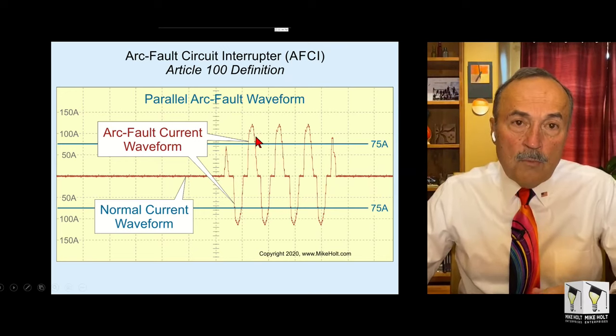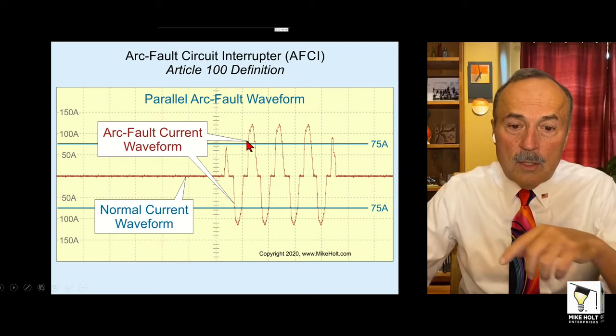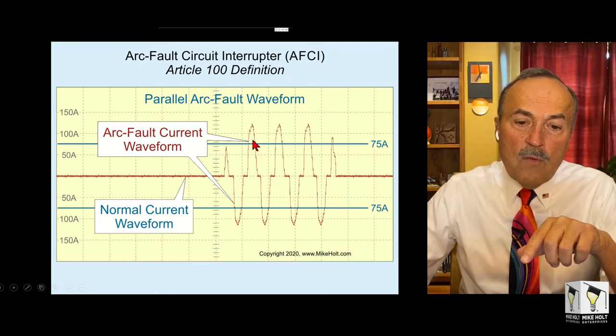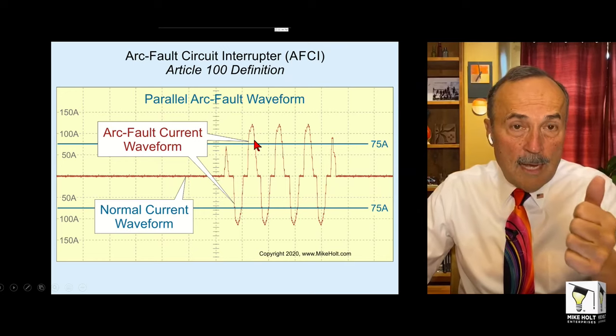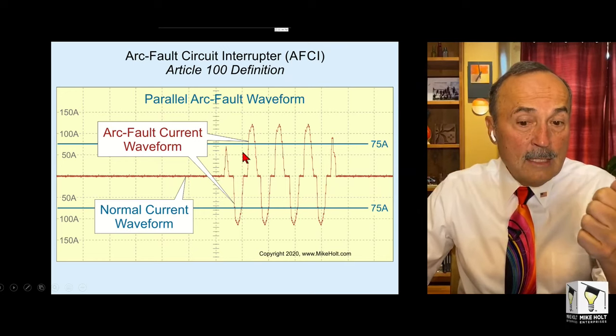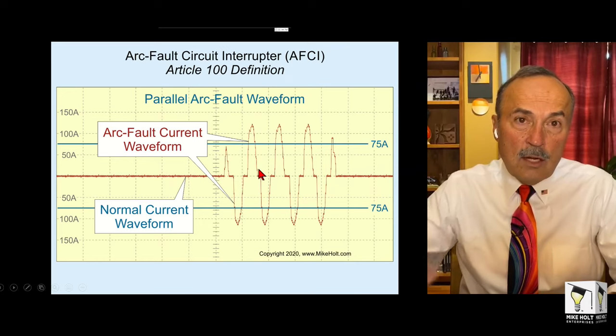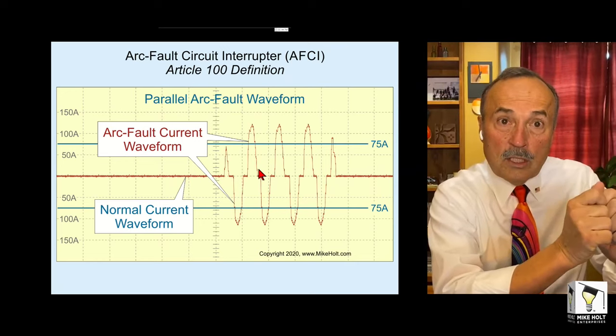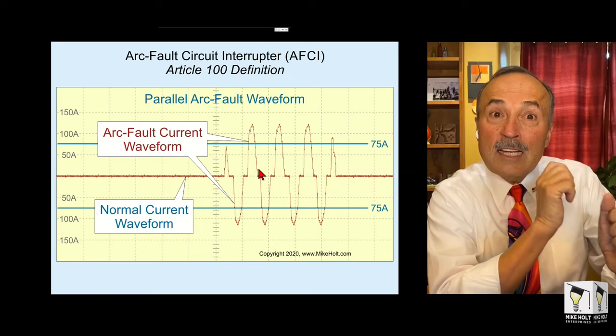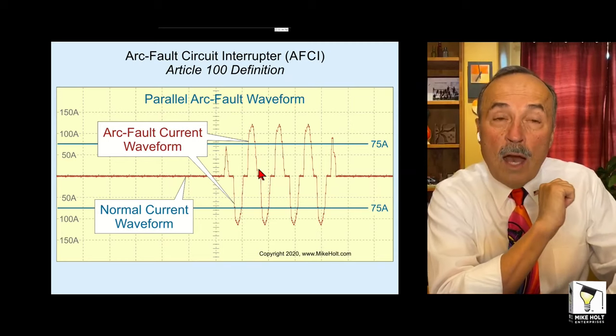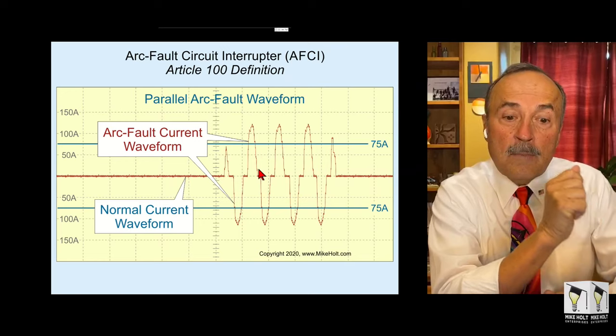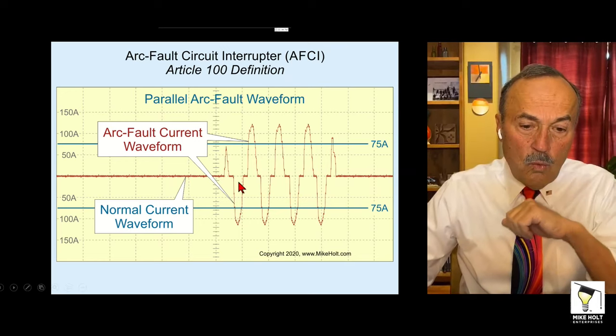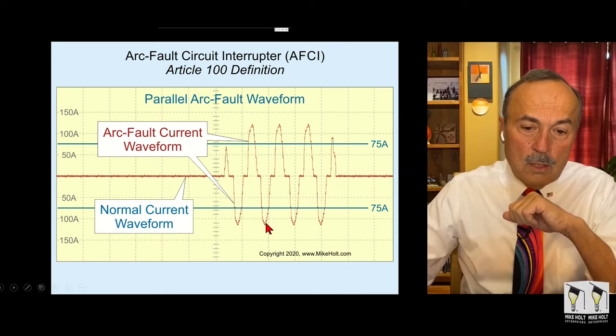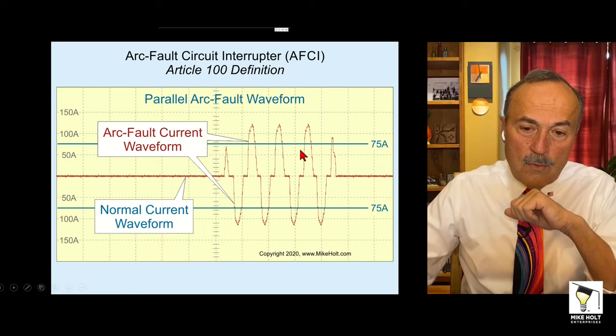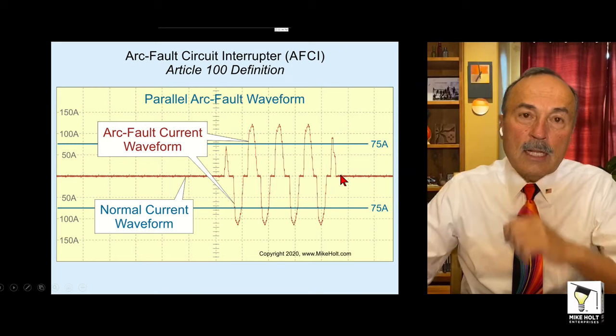And then what they do is they look for this. Number one, in a parallel sensing mode, that waveform has to be over 75 amperes peak. So it looks for that. Is it over 75 amperes peak? Yes. Then it takes that signature and does a quick compare with this computer to find out, does this match anything that we know of? And if it says yes, it actually does, then it counts it. It says, okay, well, that's one. Well, that's two. That's three, four, five, six, seven, eight, and it is gone.